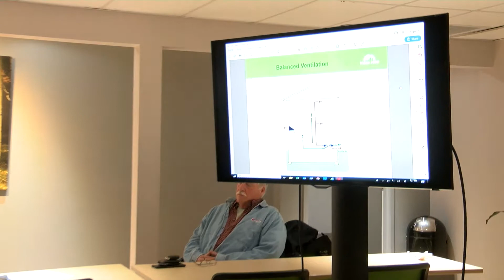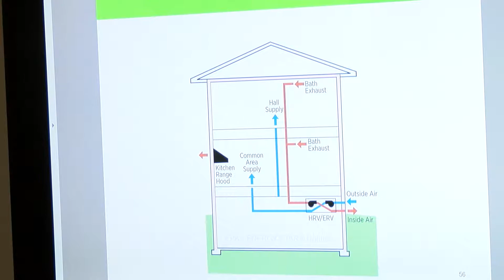The last ventilation type, or mechanical ventilation, is balanced, like Mike put in his house. So Mike, please feel free to kick in on this. Sure. Yeah, so the advantage of the balanced ventilation is that you can take air out of the house exactly where you want to and bring fresh air where it's most needed. So places like bedrooms at night, you can bring fresh air into the bedrooms at night. You can pull air out of places like bathrooms and kitchens, where there's high moisture content. So not only can you put spot solutions in your house where you need fresh air and need to pull out exhaust, the balanced ventilation is the only method to actually recover the heat or the air conditioning that you just put into your house.